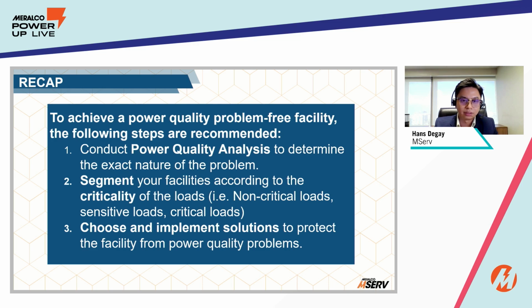So susukat po tayo para malaman. Basically, we either recommend installing at the upstream to determine the incoming power. And then if you have a suspect load, we determine it by measuring at the point of the problem, for example a specific motor or a specific branch. And then, once you determine which of your equipment is sensitive and which is not, you can segment your facilities by classifying them as non-critical loads, sensitive loads, and critical loads. By then, you would know which ones to protect. Choose and implement solutions to protect the facility from power quality problems.